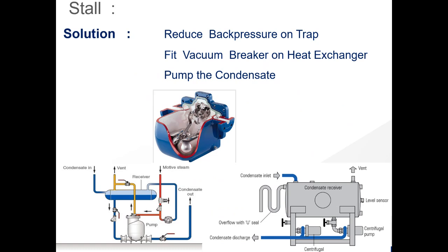Pump the condensate. As you can see here, we have the APT that I just mentioned, the automatic pump unit. This is a larger vessel, an MFP, for larger flow rates. It's still a pump trap with a vessel, a receiver, to collect condensate. And here we have the electrical solutions that many of you will have on site: an electrical pump and a receiver that receives the condensate and pumps it back to your system.